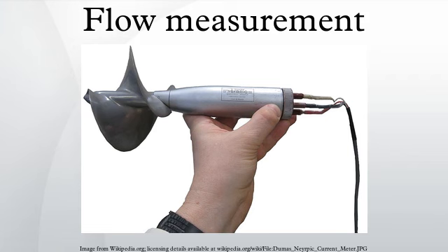Transit time method: for pipe flows, a so-called transit time method is applied where a radiotracer is injected as a pulse into the measured flow. The transit time is defined with the help of radiation detectors placed on the outside of the pipe. The volume flow is obtained by multiplying the measured average fluid flow velocity by the inner pipe cross-section. This reference flow value is compared with the simultaneous flow value given by the flow measurement to be calibrated. The procedure is standardized. The best accredited measurement uncertainty for liquids and gases is 0.5%.